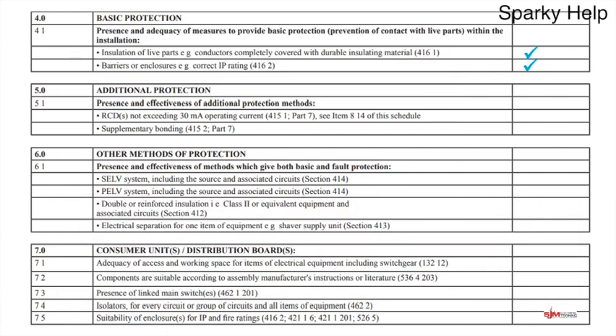If you've got any of those, it'll be a tick on this page, but when you get to 8.14, you'll tick and narrow down exactly where your RCD is actually protecting. So the chances are that is going to be a tick. Supplementary bonding, often known as cross bonding, where you might go across the hot and cold and the flow and return and all of those bits and pieces, and typically the sizes you're looking at for these is minimum of 4 mil unprotected. If you decided to put it in conduit, then it would be a 2.5 that you would put that in.